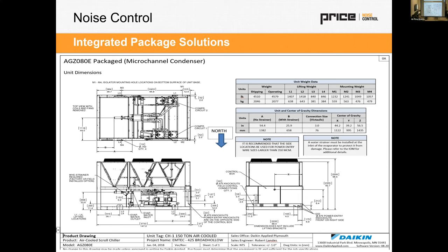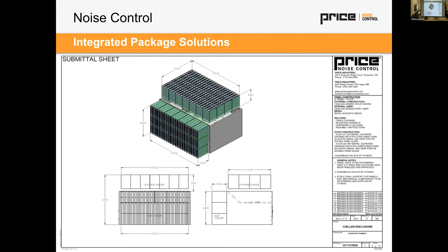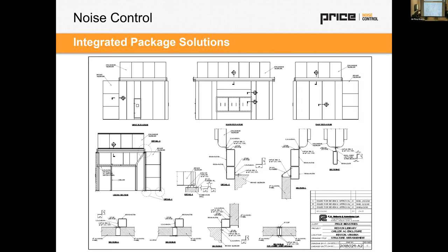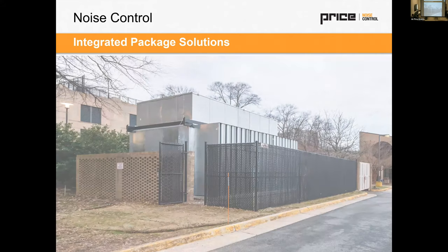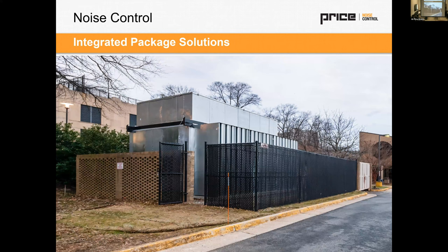We do a lot of work with chillers, and chillers make a lot of noise from a variety of areas, the compressors, the condensing fans. There's a lot of chiller noise solutions that we've developed. This was a unique one that required a lot of attenuation, as well as inlet and outlet silencers and an acoustic panel surround to knock down noise into the community. We often work together with structural engineers as well. We have a few experienced structural engineers on our team that we design snow load, wind load, and seismic structural constraints around. This is that job in reality here.